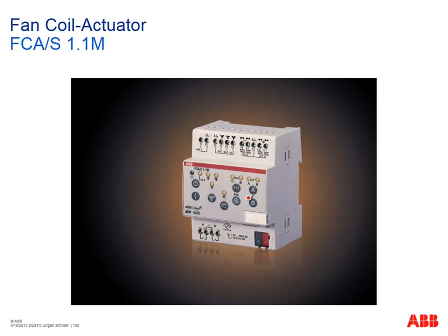So this so-called fan coil actuator is a device to control standard fan coil units. We have here on board two electronic outputs. One output to control our valve drives for heating, and another output to control the valve drives for cooling. It is possible to connect thermoelectric valves or also 3-point valve drives like motor valve drives, like Thorsten explained before. Additionally, we have here the output to control the fan with up to 3 speeds, and a switch output for switching the light for example, or some fan coil units have an additional electrical heater inside, and with this relay we can switch on this electrical heater maybe in the winter time to heat up very fast the room.